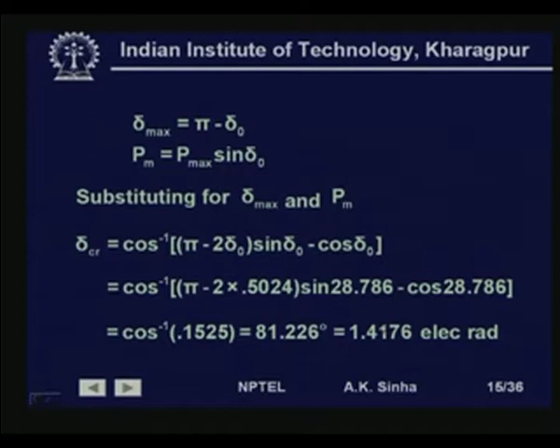Now, delta max, as we have seen, is equal to pi minus delta 0 and P m is equal to P max sin delta 0. So, substituting for delta max and P m, we will get delta CR is equal to cos inverse of pi minus 2 delta 0 into sin delta 0 minus cos delta 0. Substituting the value of delta 0 in this relationship, we will get cos inverse of pi minus 2 into 0.5024 into sin 28.786. Here, as we said, whenever we are using delta 0, we write the value not in degrees, but in radians. So, 2 into delta 0 in radians, that is 28.786 into pi by 180. So, this is equal to this sin this much minus cos this much. This, when we solve, we get as 1.4176 electrical radians, which we can convert into degrees if we want.